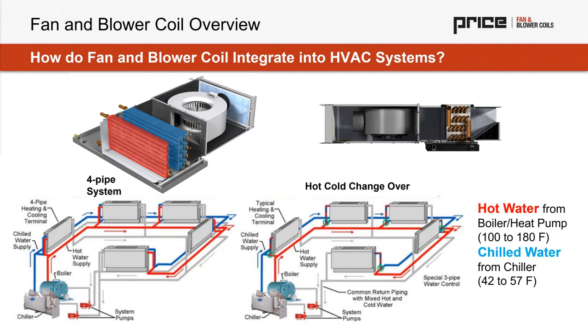And on the right, we also have a two-pipe solution, so a hot-cold changeover coil. This would be a two-pipe coil, a single coil that would be used for either heating or for cooling. The diagram in the bottom right shows a special three-pipe water control system, which is less typical. That is used on medium and small commercial projects, fit-out projects. Primarily, we would still see four pipes, two supply, two return, and then just changeover valves located directly at the fan coil. This is becoming more popular as our supply hot water temperatures are dropping. Anecdotally, I've seen a lot of projects with air source heat pumps where maybe we only have 100 degree supply water. So having a larger heating coil, heating apparatus can be very beneficial to the design of the building.